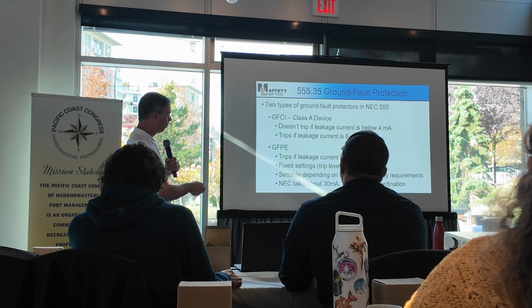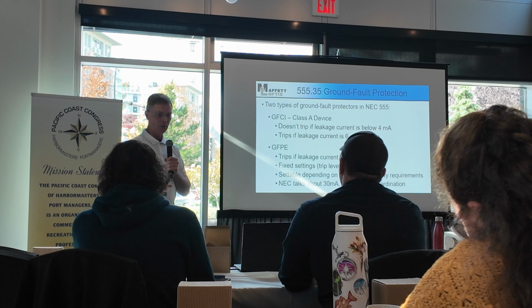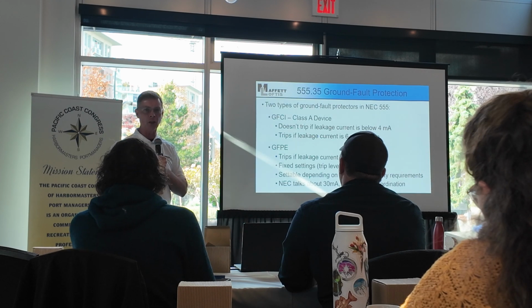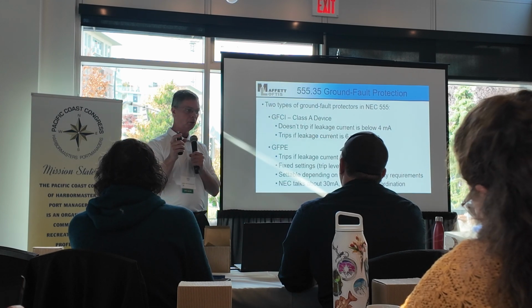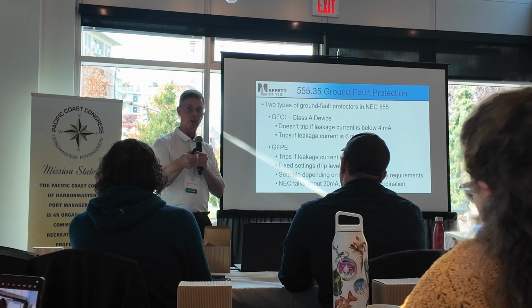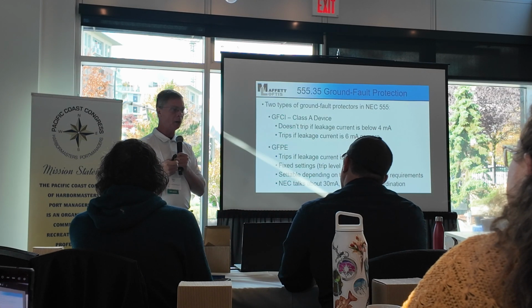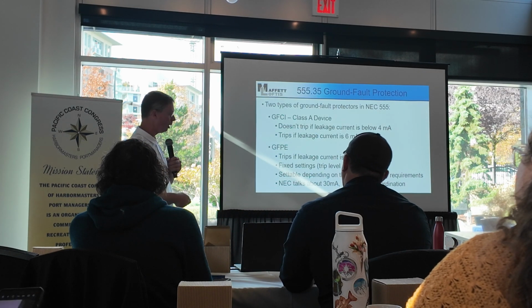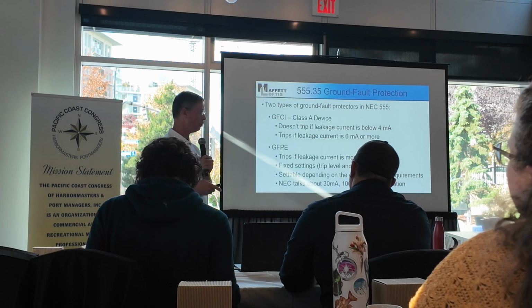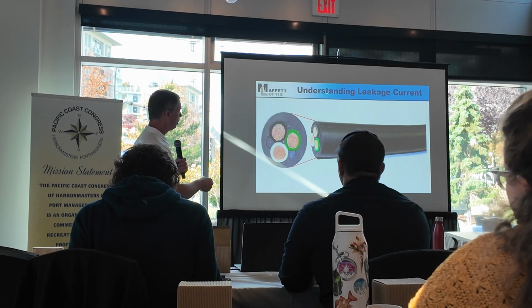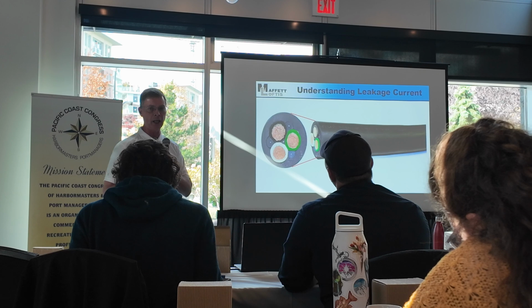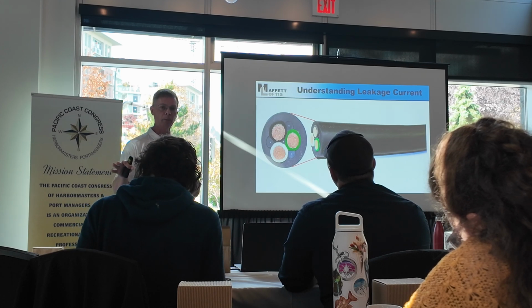And they both have locations and homes in the marina. The 15 to 20 amp GFCI receptacle, which you plug the extension cords into, that's a GFCI. The shore power is at this 30 milliamp, and the branch circuit feeder is at 100 milliamp GFPE. But I want to go through this class, the last part of this, understanding NEC leakage currents, as I've talked about it a lot.